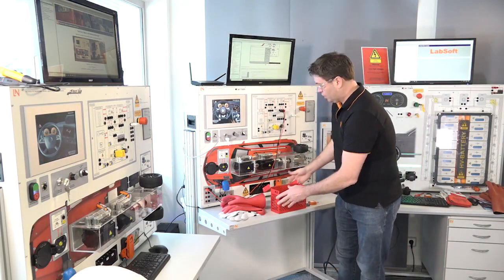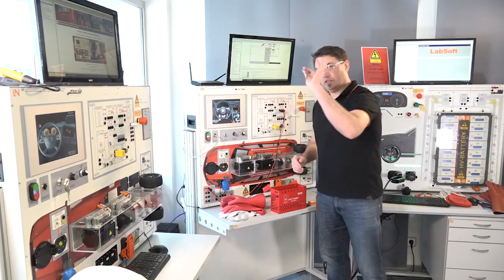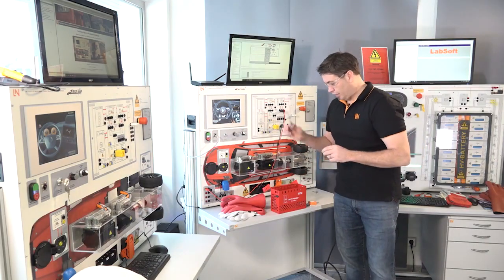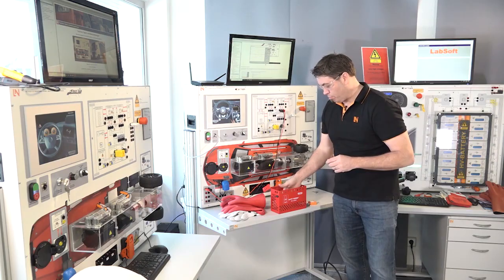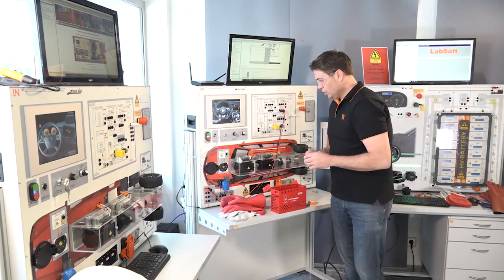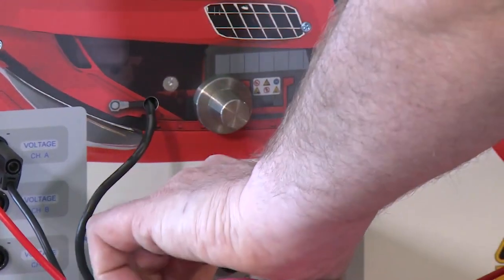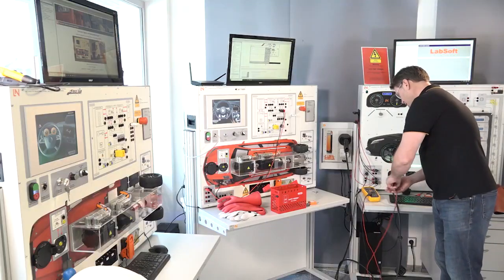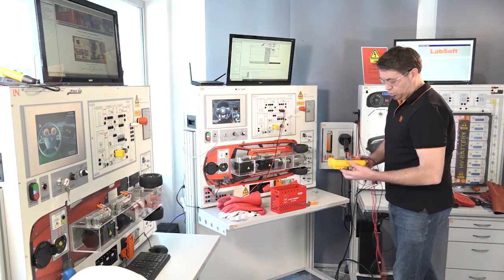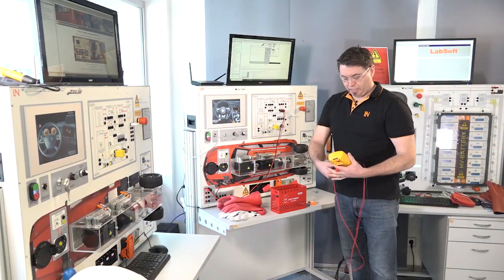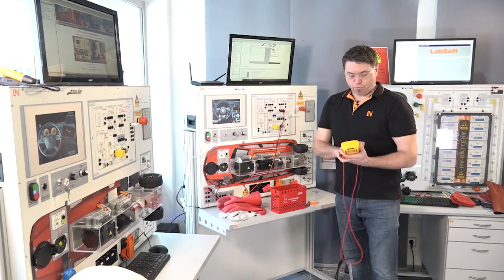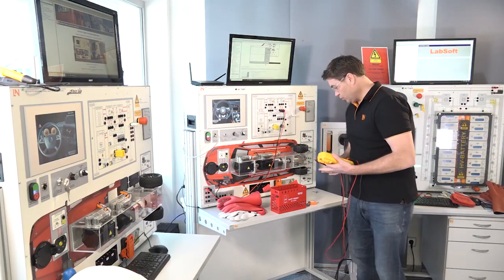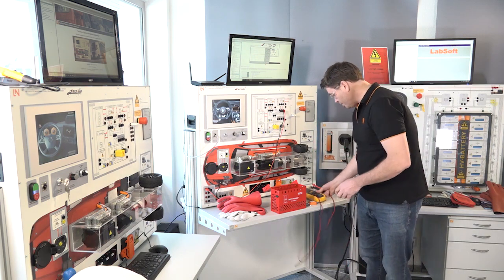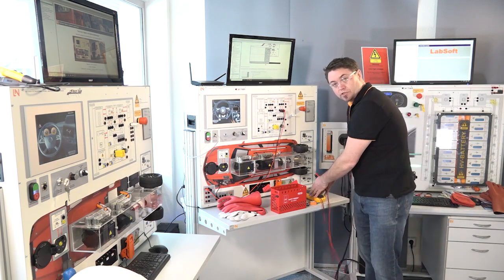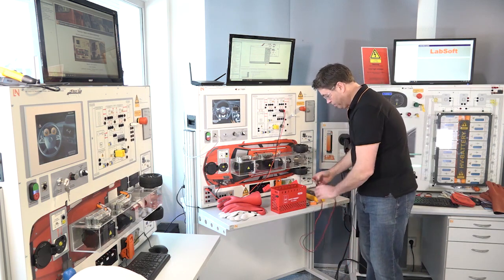What we need to do from there is take the ignition key and put that inside of our box, and disconnect the 12-volt system. We also need our measuring device. In this case we need a category 3 rated multimeter so that we can measure the high voltage, and we're also going to use this one because it's an insulation tester at the same time.